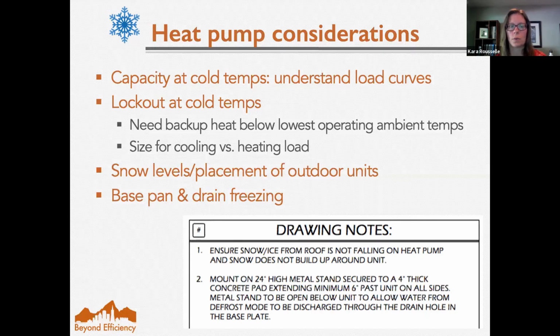This applies for air-to-air and air-to-water heat pumps, and we haven't talked about it yet, but the standalone heat pump water heater, the outdoor unit for that, they all have the same guidelines. Some of them, Sanden has more specific ones. So if you are specifying one of them, make sure you're checking with the manufacturer to make sure that you are covering all of their cold climate guidelines.